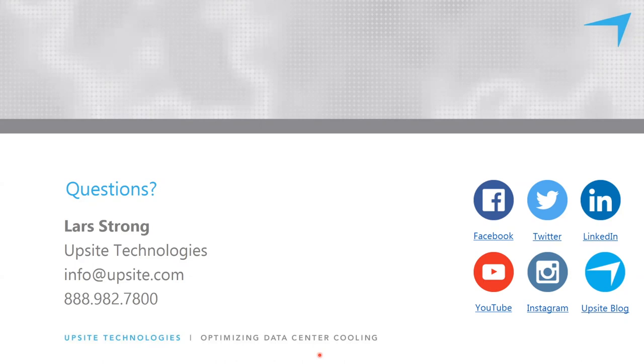Next one, with a limited budget, what solution do you recommend starting with first to have the biggest upfront impact? It's either between, and it goes out of this presentation. So, you know, the holistic considerations are, it's either addressing airflow management at the raised floor level or at the rack level. Quite often I've seen the most benefits result from making sure blanking panels are installed in every single open U space. Really dealing with rack airflow management.